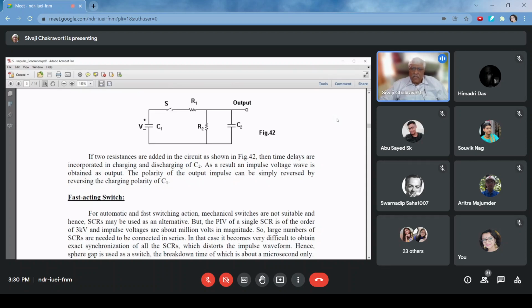Once C2 is charged to its peak value, then the voltage of C1 and C2 is the same, as I stated earlier. Then you can see both C1 and C2 have one resistance, that is R2, in parallel. So C1 and C2 will start discharging through R2, and the moment they start discharging, the voltage of C2 starts decreasing. So when C1 is charging C2, the wave front is generated, and that is over a resistance R1. So that time constant actually determines the wave front time. And after reaching the peak value, both C1 and C2 discharge through R2, and this discharge time constant determines the wave tail time. So it is a quite simple circuit, which in fact, if you are good at simulation, you can even do a very simple simulation and see how this is generated.